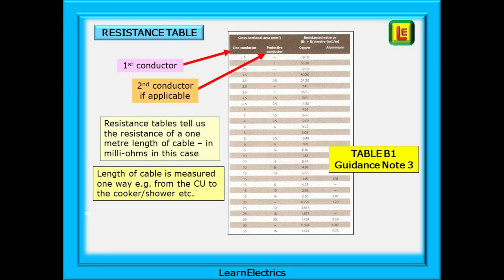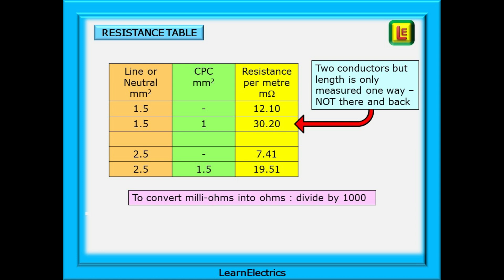The resistance value we should expect can be calculated using the resistance data in table B1 of guidance note 3. The resistance tables tell us the resistance of a 1 meter length of cable in milliohms, and we can calculate the resistance of one conductor or a pair of conductors depending on how we are testing the circuit. Note that we only use a one-way length for the cable even if we are measuring two conductors - the table data takes account of this. For example, table B1 shows that one meter of 1.5mm conductor has a value of 12.1 milliohms, and a one-meter length of 1.5 by 1mm twin and earth is 30.2 milliohms. To convert milliohms into ohms, divide by 1,000.